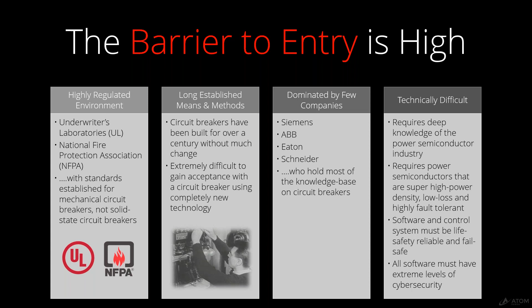On top of that, it's dominated by a few companies that own the entire electrical industry, the ones you're probably familiar with, like Siemens, ABB, Eaton, Schneider Electric. And to create a solid state breaker, you have to have in-depth knowledge of semiconductors, how to create a semiconductor for power that can have low losses and high fault tolerance. You also need software and control to control that semiconductor reliably and safely, have it fail safe, and also have it extremely secure from cybersecurity events so that you can't hack into the power system.